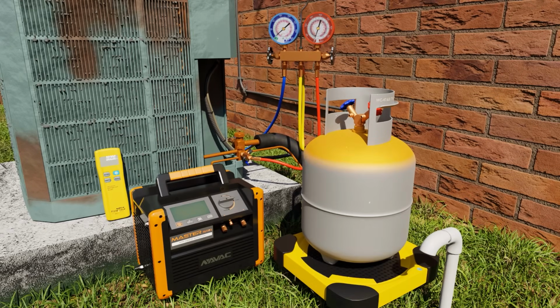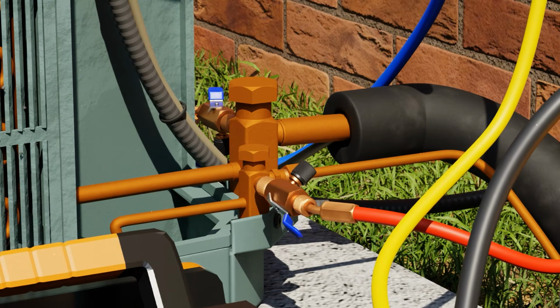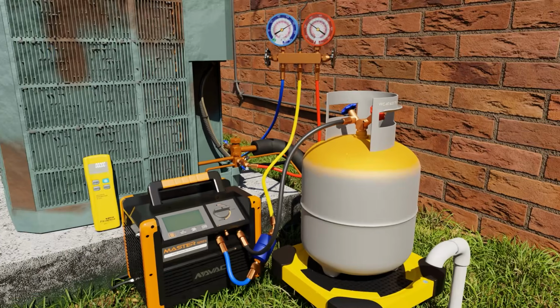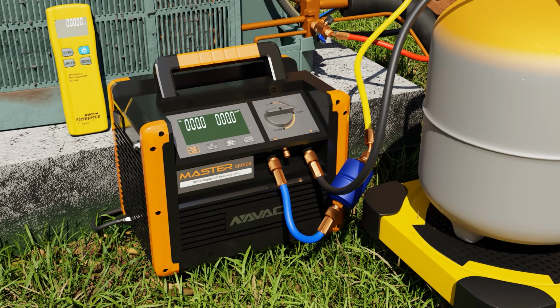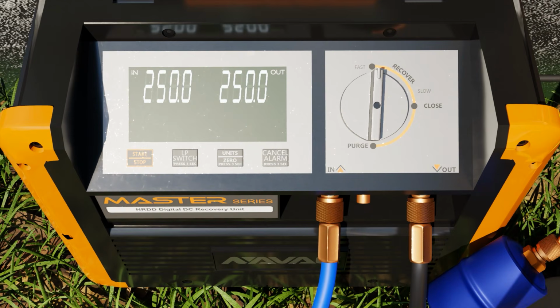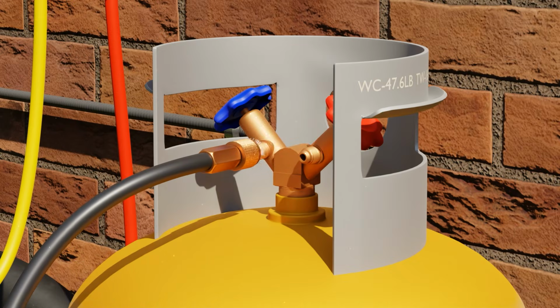Once you get all your hoses connected, remember to attach a liquid line filter dryer in line to protect the recovery machine. Open your core tools on the system and open your hand valves on the manifold. Purge the hose going into the recovery machine to make sure you're not bringing in air. Then you purge going into the tank.